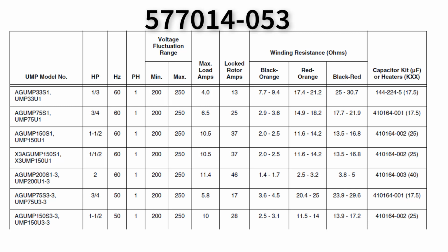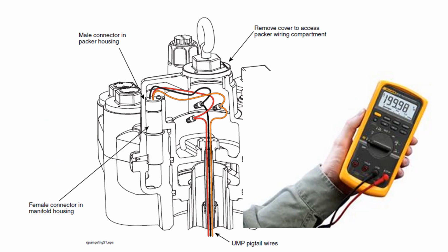If there is no amperage draw, the motor windings could be open. With power off, measure the resistance between the black and orange wires. Refer to the service manual for the correct winding resistance. If the resistance is infinite, the overload may have been tripped, or you have an open circuit.